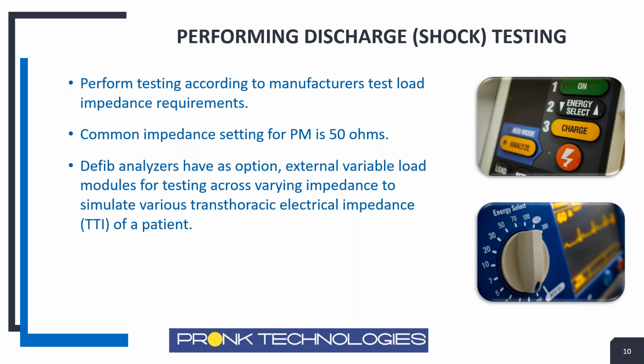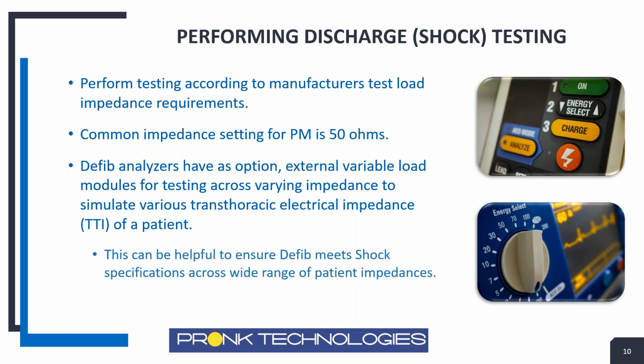So if you're doing a discharge test at 100 joules at a 25 ohm load, you may have a particular value delivered. But if you're doing it at 175 ohms, you could very well see that the defibrillator shock output could be a little different. It should still be within spec, but it could be different. This could be a good tool for us to verify that the defibrillator works properly across wide ranges, so that we'll have that much more confidence that it meets its specifications. It doesn't necessarily need to be done for PM, but it could be a good best practice to utilize, particularly if you're investigating an issue reported by the clinicians, or if you're doing repairs to the defibrillator.